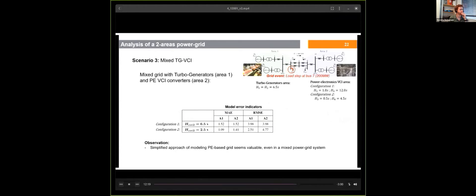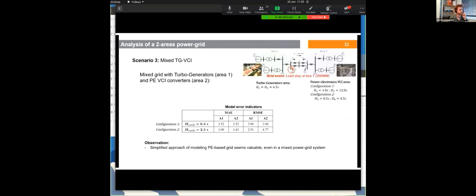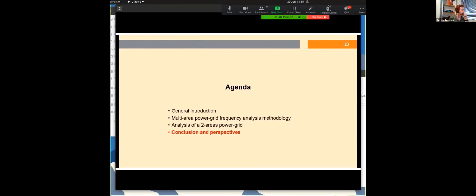In the last scenario, we consider a mixed configuration with turbo generators in area 1 and power electronics converters in area 2. In area 2, two configurations are tested: an aggregated inertia of 6.5 seconds for configuration 1, and 2.5 seconds for configuration 2. In both cases, the model error indicators remain at acceptable levels.